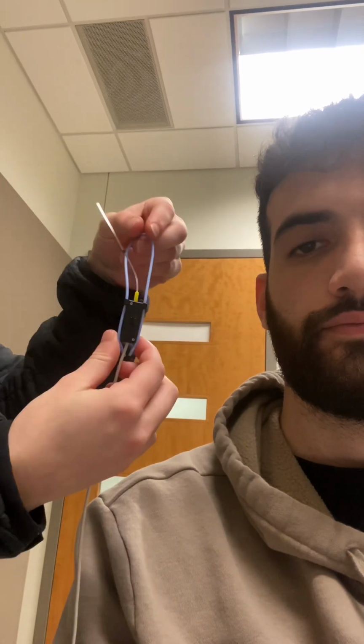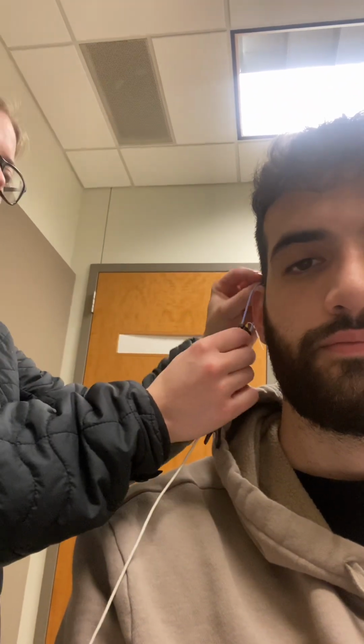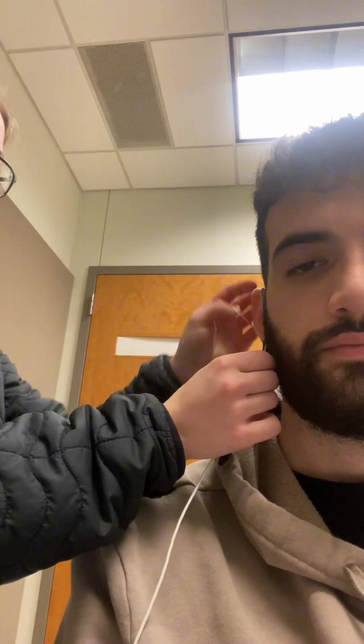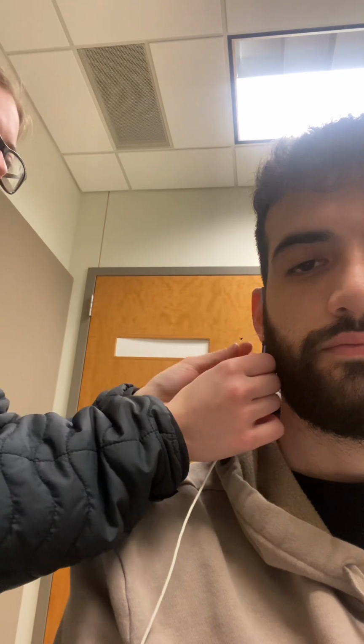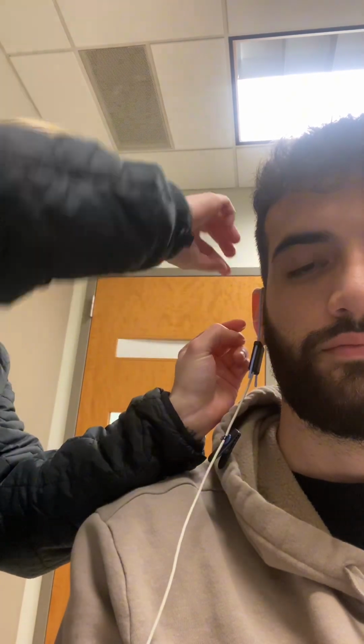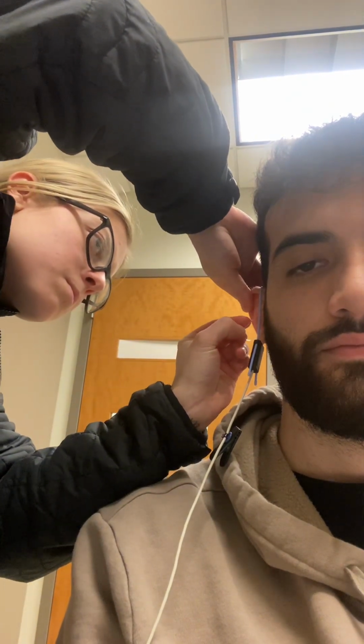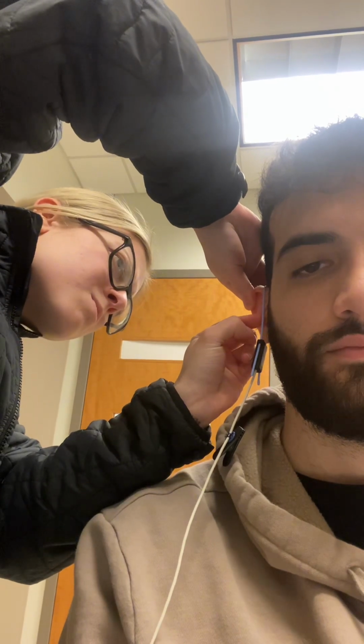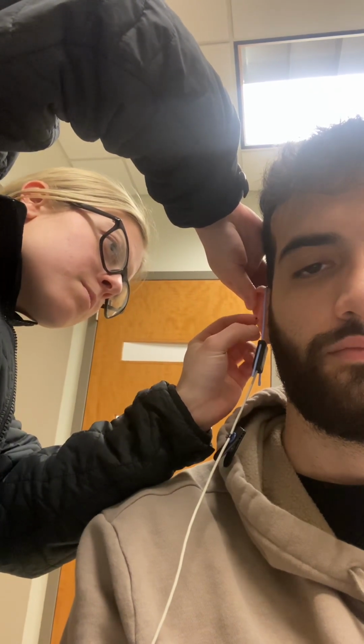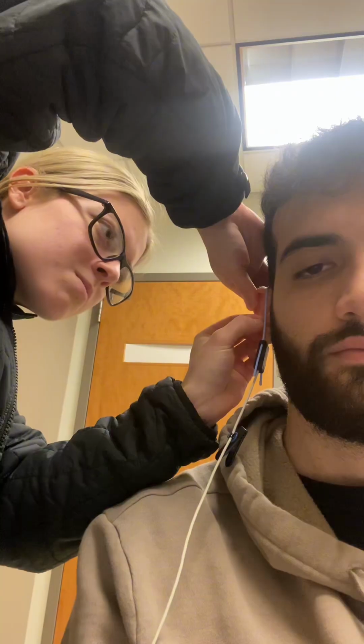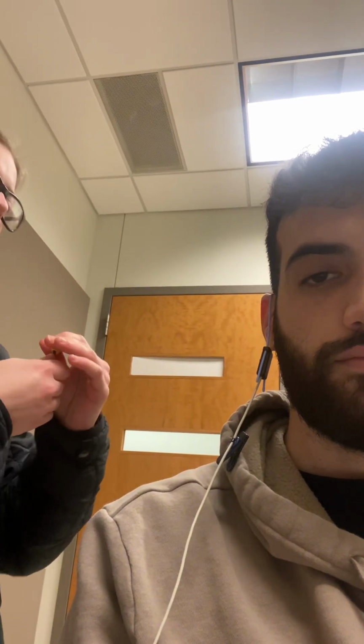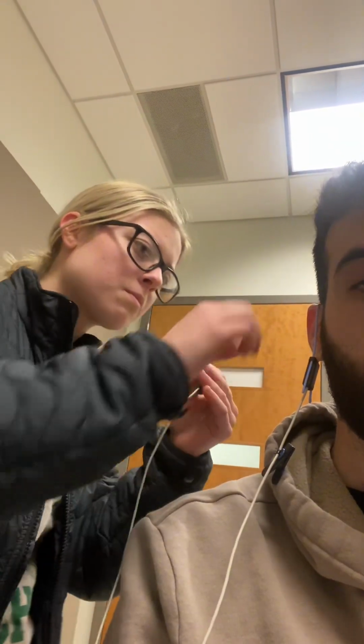We'll need to make sure the reference mic is facing outside, and we want to make sure that it's flush right under the earlobe. We're going to place the probe tube into the ear canal, and we want to make sure it's 2 to 5 millimeters away from the eardrum. Then we're going to take an insert foam tip and place it on the RECD jack and place that on top of the probe tube into the ear canal.